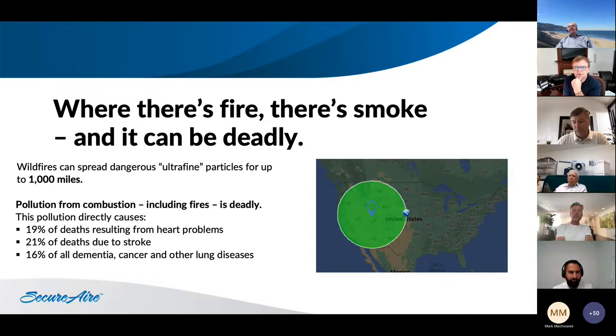They justify it from a health point of view, wanting to use 100% outside air. It uses a lot of energy, but they have heat recovery coils, so regardless, that's 100% outside air. In the wildfire event, what we did was, one, shut interior doors, so the smoke might come into the front lobby but doesn't migrate deep into the hospital. Then we went to the outside air filters and attached a 1-inch layer of carbon filtration as a temporary mode during wildfire smoke events. That actually became part of the policy.